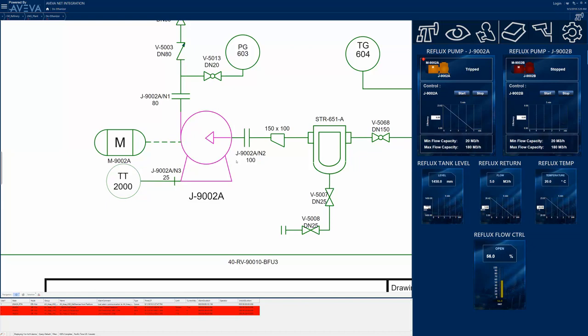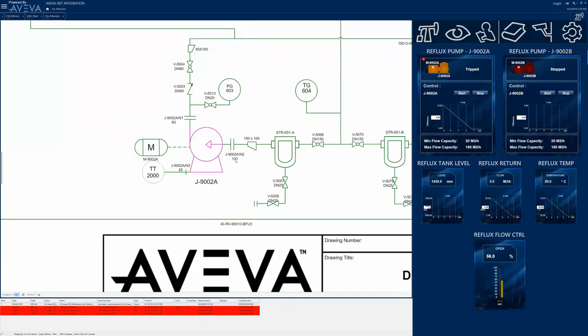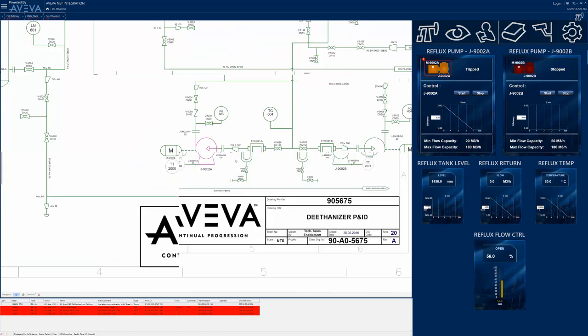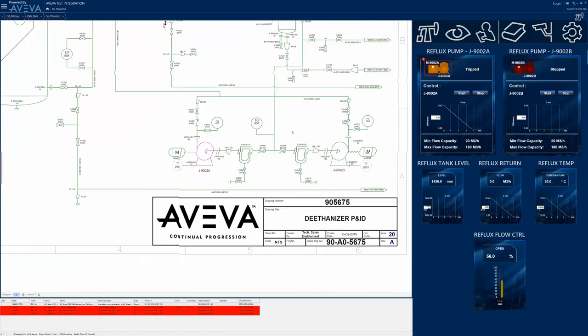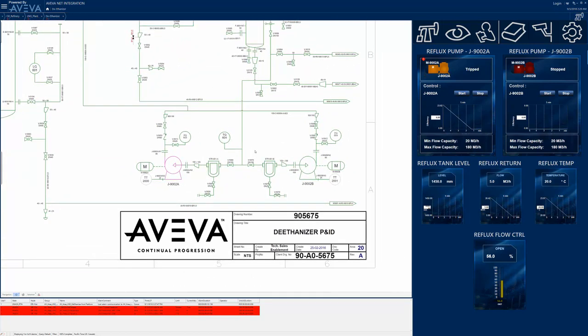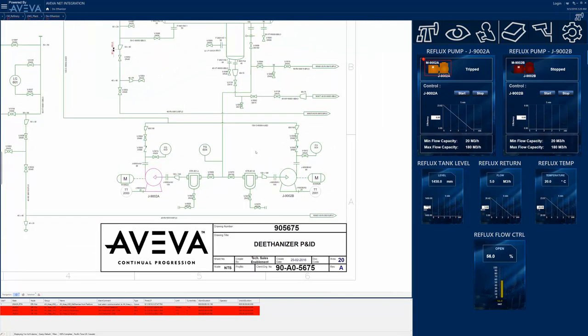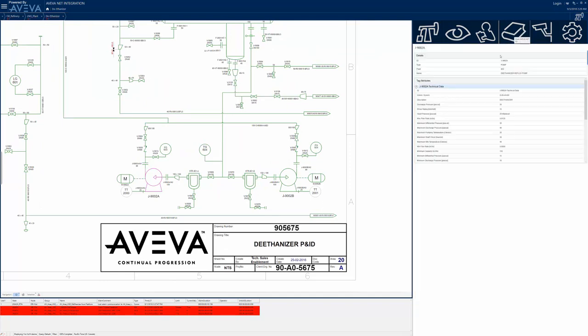The operator zooms out of the P&ID to get a better understanding of the technical context of the selected pump, and verifies that the troubled pump appears to have a backup partner, J9002B, which is currently idle.